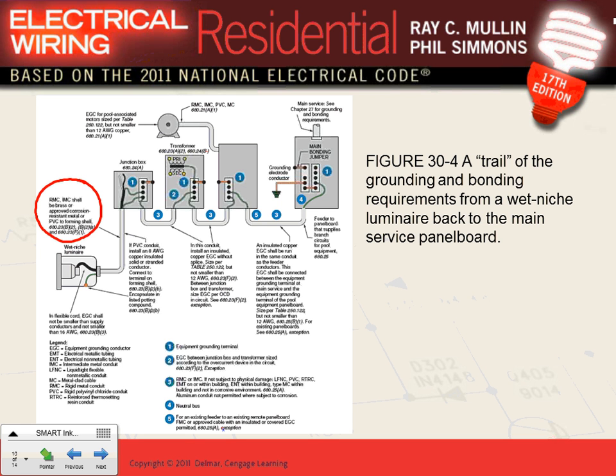You have to use rigid or intermediate or PVC conduit to wire it. You have to have an isolation transformer that feeds it. You have to have a continuous number 12 grounding conductor that goes all the way. Can you guys see that? See that grounding conductor, number 12, that goes all the way to the light? You have an isolating transformer. You have a box. If this light is fed from a higher voltage, you have to put it in a GFCI, so the circuit breaker has to be GFCI.